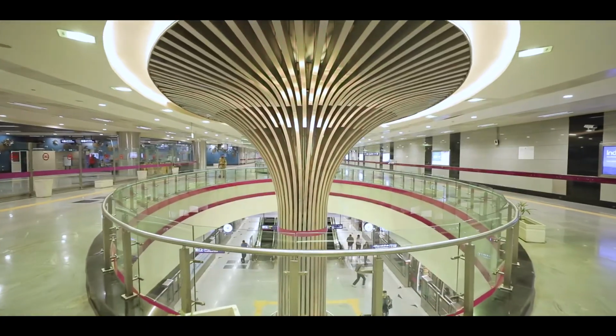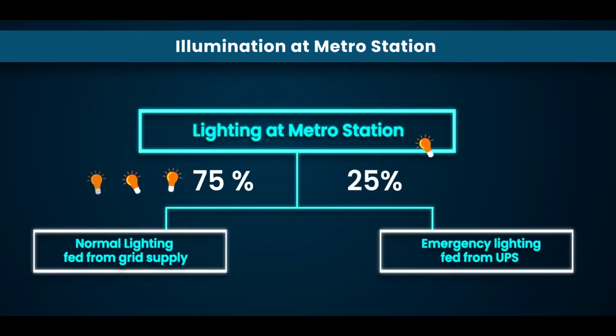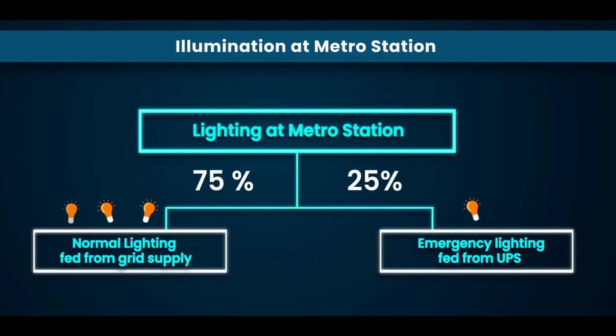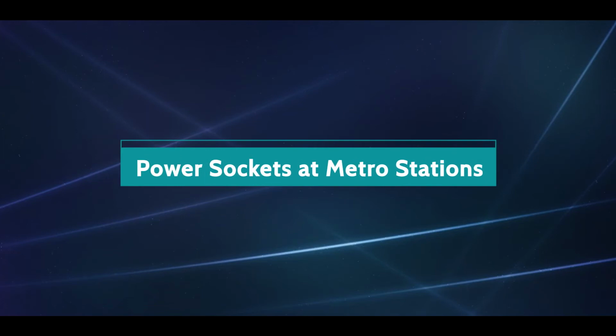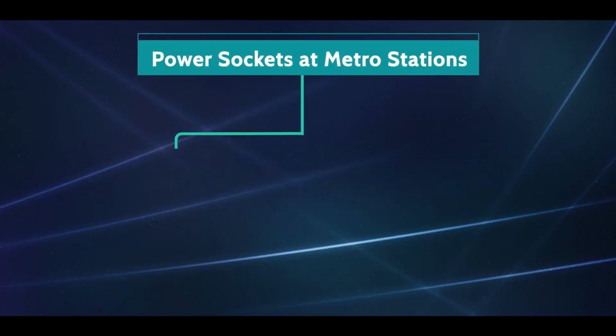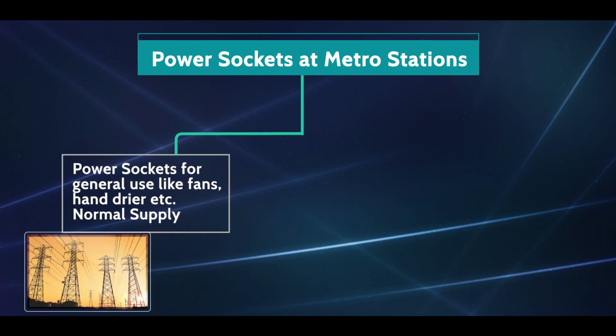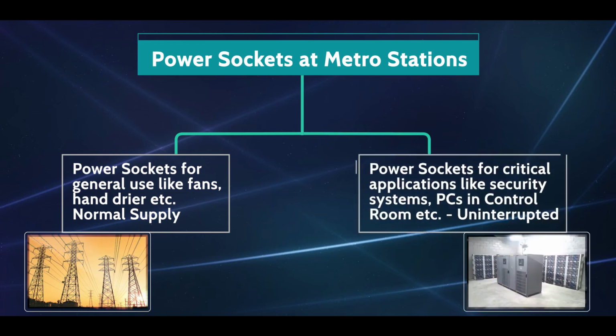Illumination at a station is divided into two categories of load. 75% of lighting is given normal supply from the grid, whereas 25% of lighting is given uninterrupted power supply. Similarly, power sockets at a station are divided into two categories of load. Power sockets for general use like fans, hand dryer, etc. are provided normal supply, whereas power sockets for critical applications like security systems, various PCs in the station control room, etc. are provided with uninterrupted power supply.